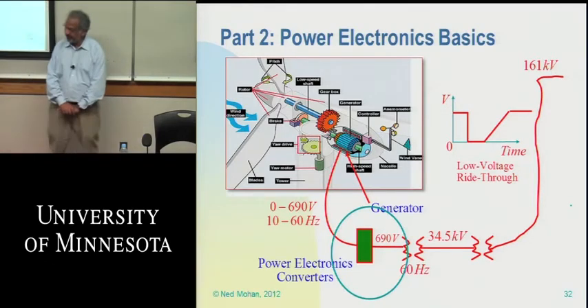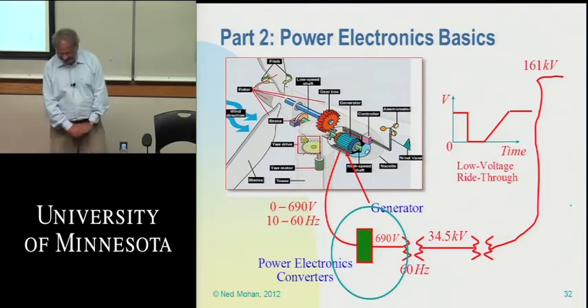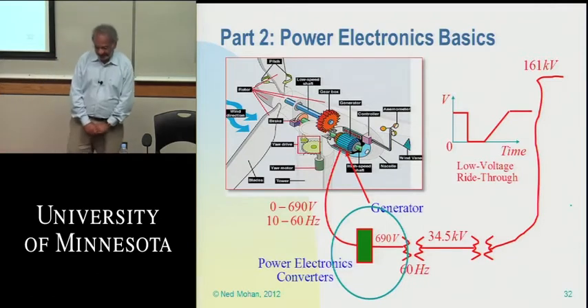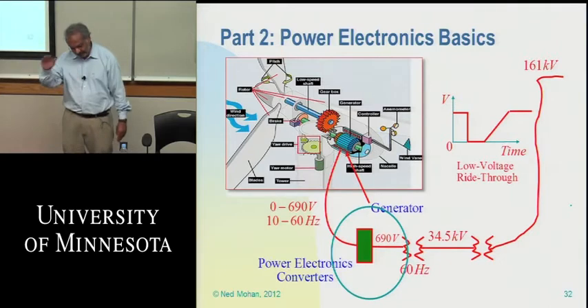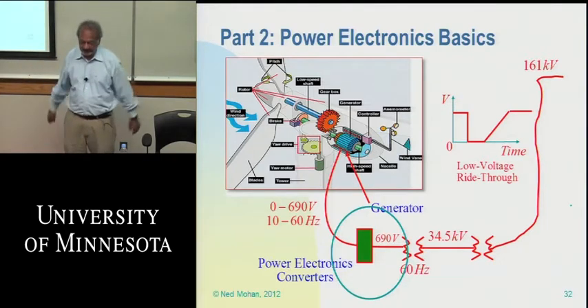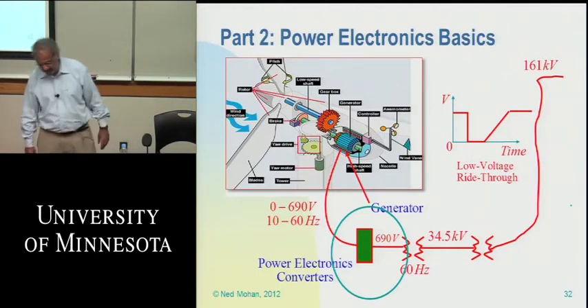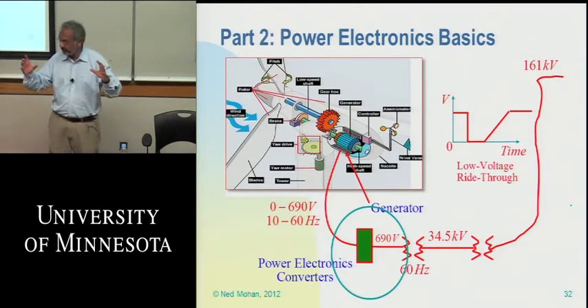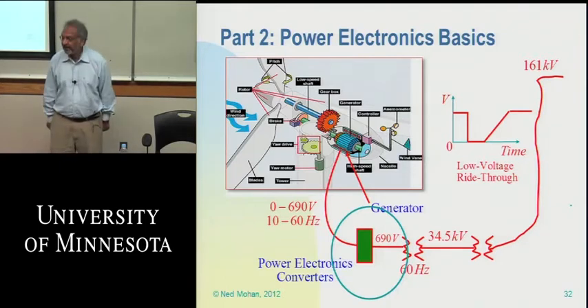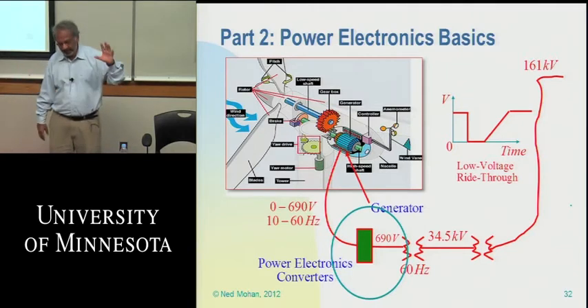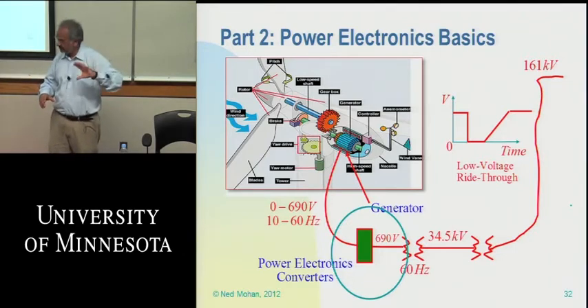We looked at the need for reactive power, and that reactive power can prevent, up to a certain point, voltage collapse. STATCOM can provide reactive power. We also saw transfer from one AC source to another AC source, and the power flow in AC systems - remember, power flow in AC systems is downhill on angle. Unlike DC systems, where it's downhill on voltage, from 100 volts to 90 volts, in AC systems it flows from leading voltage to lagging voltage. Leading voltage may be smaller in amplitude, doesn't matter - it's the phase angle that matters.